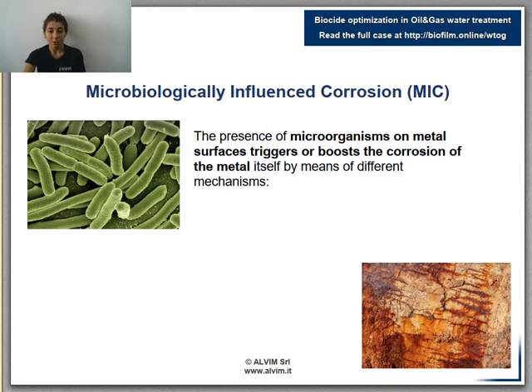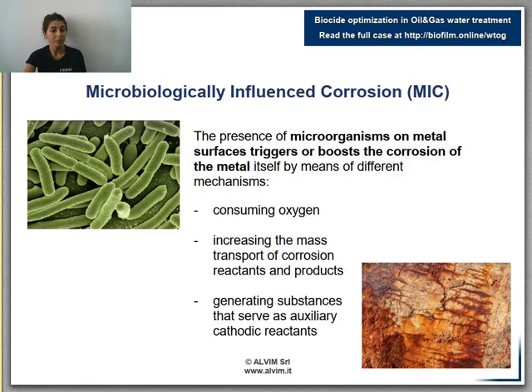MIC is caused by the presence of bacteria on metal surfaces. The biological activity enhances corrosion of the metal itself through several mechanisms. First, bacteria consume oxygen, boosting metal corrosion. Second, by increasing mass transport, corrosion is pushed to proceed. Third, bacteria produce auxiliary cathodic reactants.